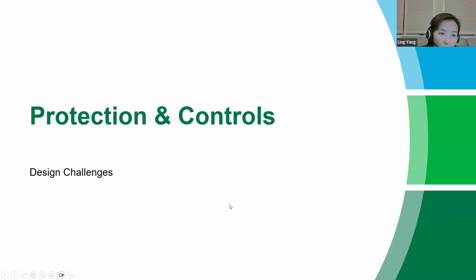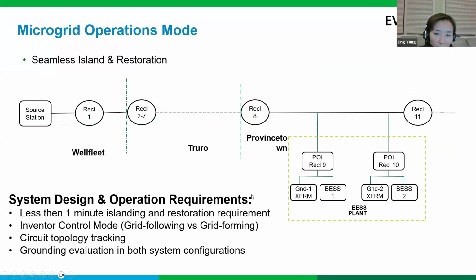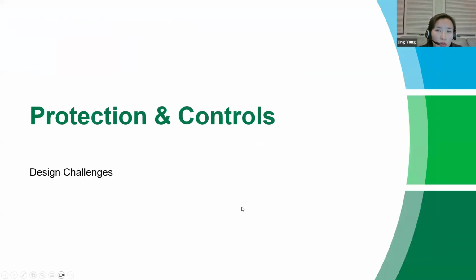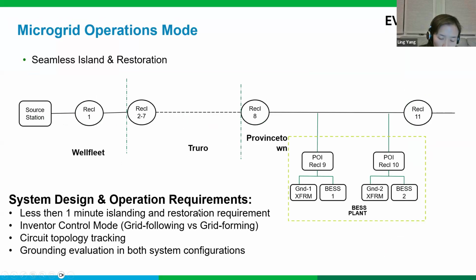I'm not a protection control person, so I'm not going to talk about protection control. I know our protection control team has spent a lot of effort doing RTDS testing, and has performed many scenarios and simulations to make sure that the protection devices are properly designed in the field. One of the design parameters I want to highlight here is that we designed the system so that the battery is able to restore the system within 1 minute. So within 1 minute, we require the island to be formed.